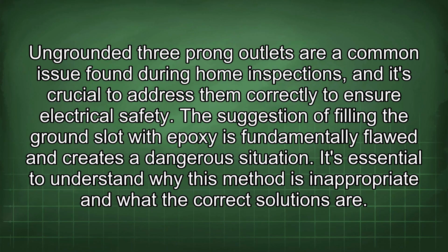Ungrounded three-prong outlets are a common issue found during home inspections, and it's crucial to address them correctly to ensure electrical safety. The suggestion of filling the ground slot with epoxy is fundamentally flawed and creates a dangerous situation. It's essential to understand why this method is inappropriate and what the correct solutions are.